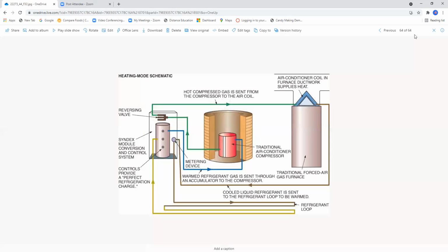And of course, in the heating mode, we have a different situation here. We've got a reversing valve. Notice that you've got one common port, and then of course you have the selector ports here between the top and the bottom. And warm refrigerant gas is sent through the accumulator to the compressor. Once again, the compressor is only designed to pump refrigerant vapor. And I believe that is the end of this presentation.